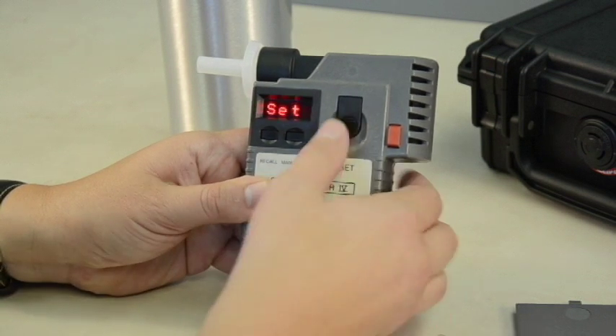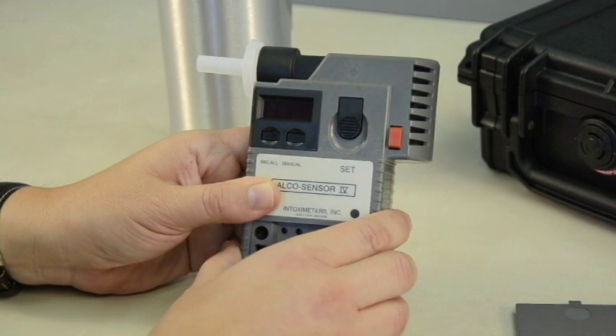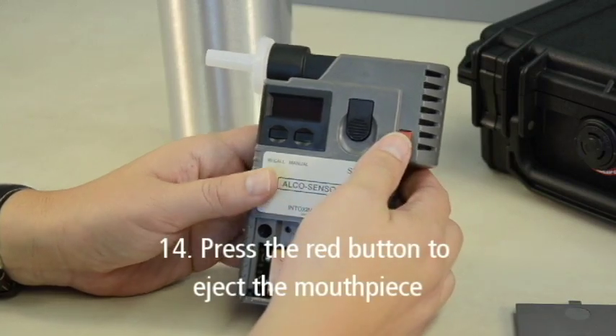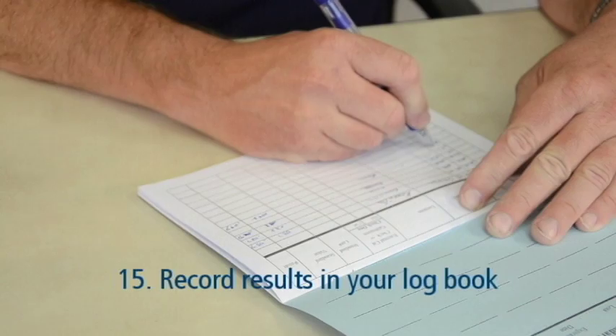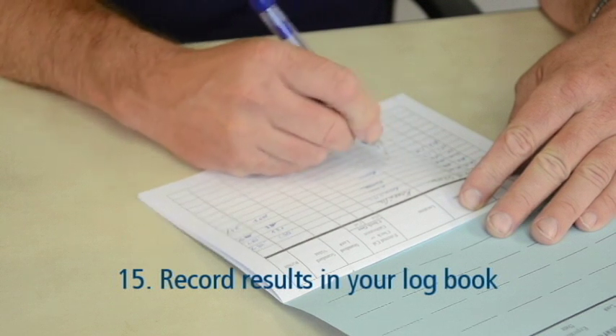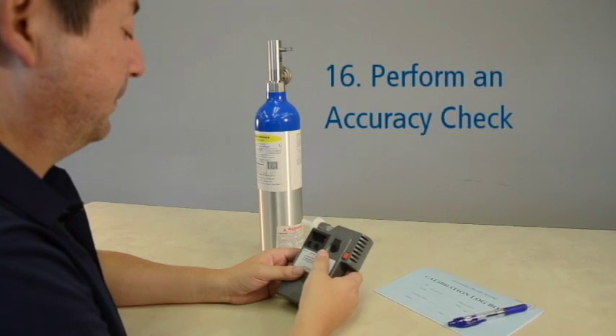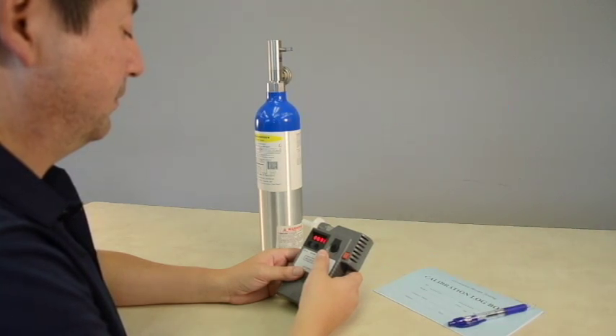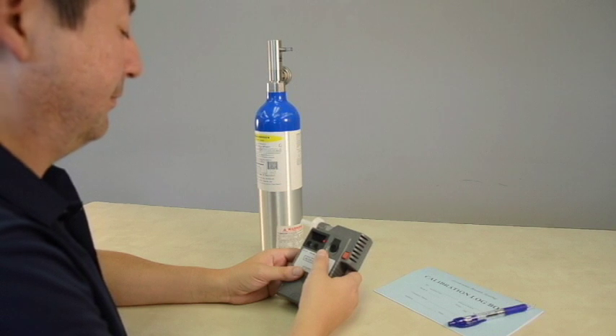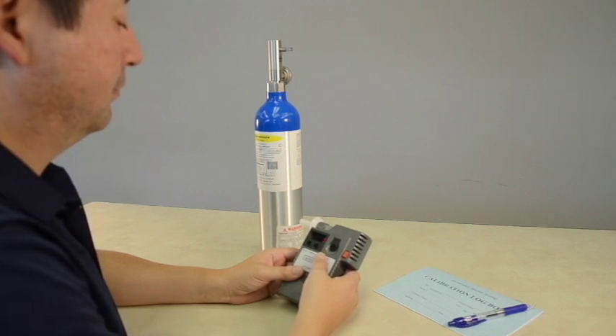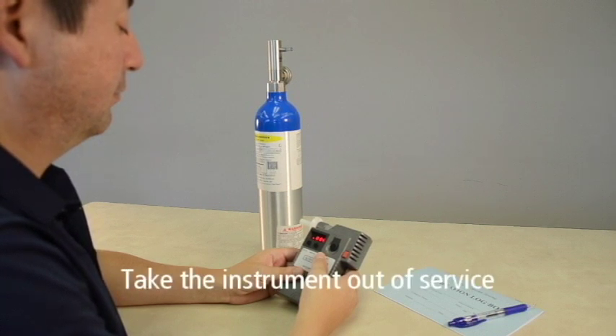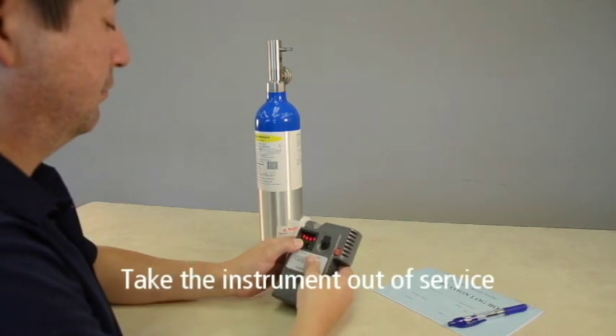This ensures the fuel cell sampling chamber is in a closed position and the device is ready for the next test. When you hear the beep, press the red button and eject the mouthpiece. Record the calibration result in your logbook. Finally, perform an accuracy check on your device to verify the calibration adjustment was successful. It is important to note if your instrument cannot maintain accuracy within an allowable tolerance following a calibration, you must take the instrument out of service and have it evaluated and serviced by a factory-trained technician.